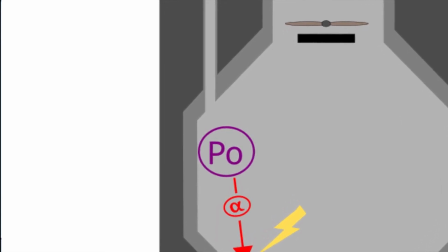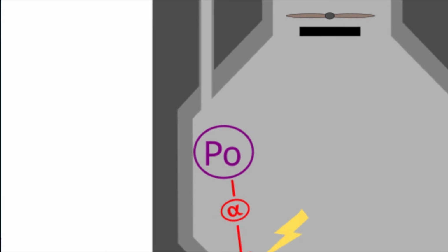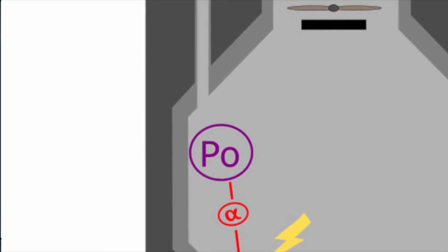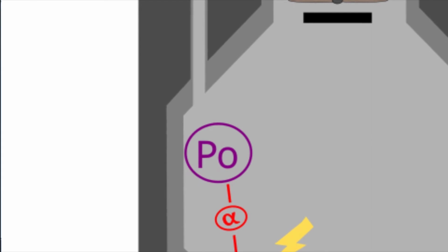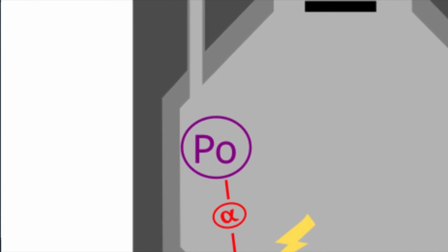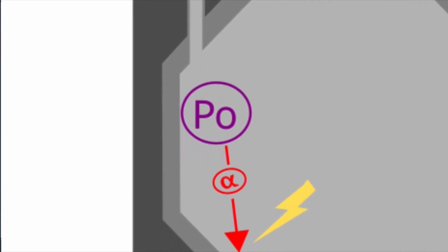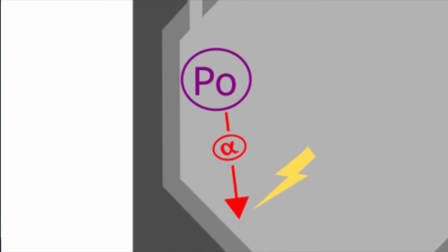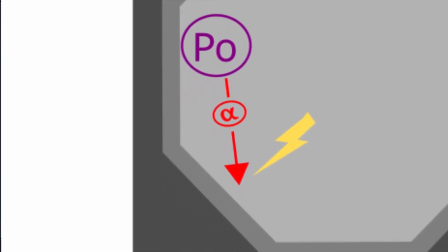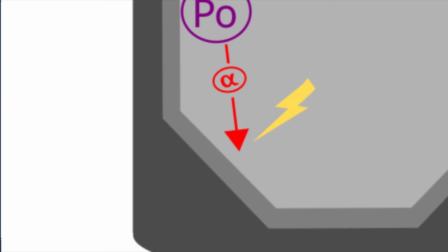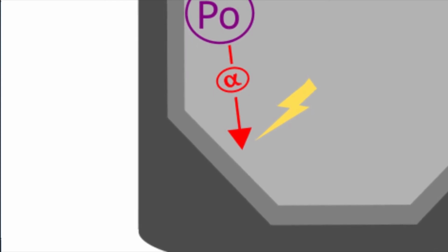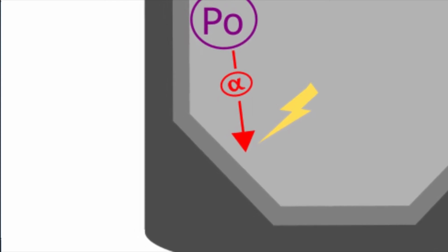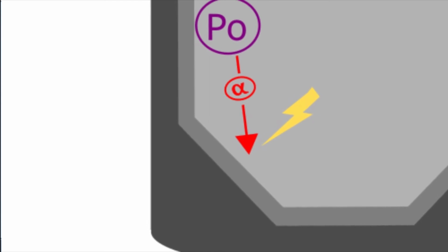The higher the radon concentration and the longer the exposure time, the more decay product gets stuck to the wall. The radon progeny continues to emit alpha particles, even after there is no longer radon in the cell. It takes about 3 hours for radon progeny to decay. In other words, unless one can determine the fractions of the pulses that are due to radon progeny, the time resolution will be quite poor, about 3 hours.